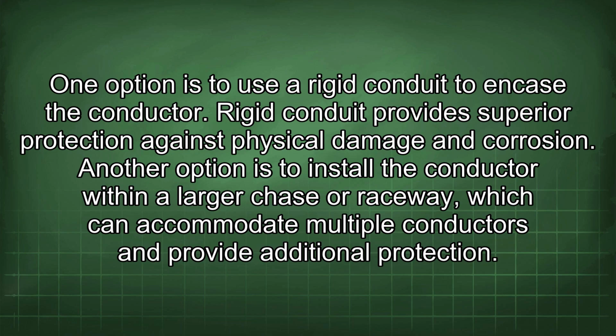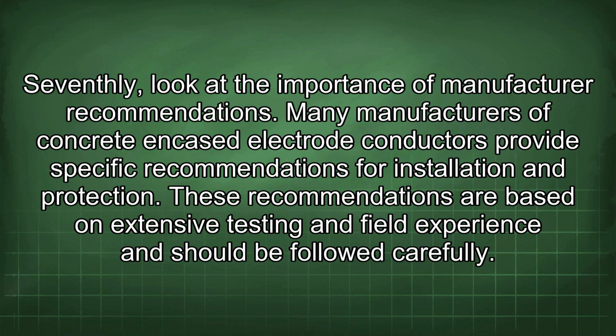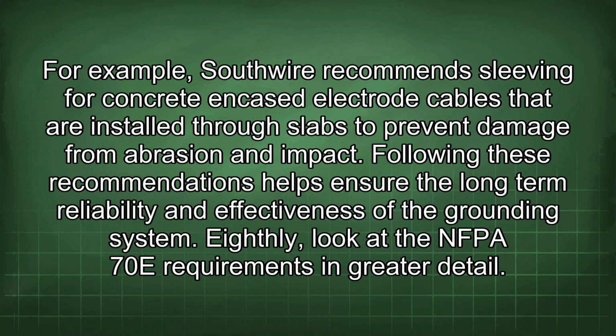Seventhly, look at the importance of manufacturer recommendations. Many manufacturers of concrete encased electrode conductors provide specific recommendations for installation and protection. These recommendations are based on extensive testing and field experience and should be followed carefully. For example, Southwire recommends sleeving for concrete encased electrode cables that are installed through slabs to prevent damage from abrasion and impact. Following these recommendations helps ensure the long-term reliability and effectiveness of the grounding system.